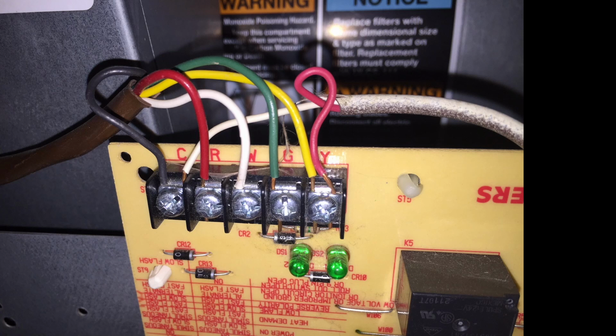Okay. Remember, I told you that if you take a voltmeter between power and common, you're going to get the 24 volts. So basically, you're legging one end of it over to common and the other one for cool. So when you kick on your thermostat and call for cool, it makes a feed over and engages power to the cool side, or Y, and it tells the outside condenser to come on. And that's why we call it control. I call it control wire. Most people do. If I go into United Refrigeration, I tell them I want thermostat wire or control wire. They know what I'm talking about.